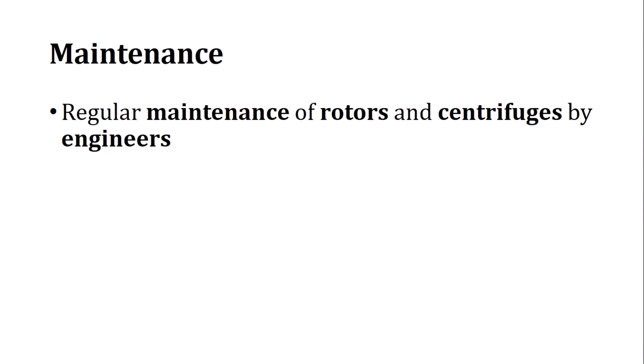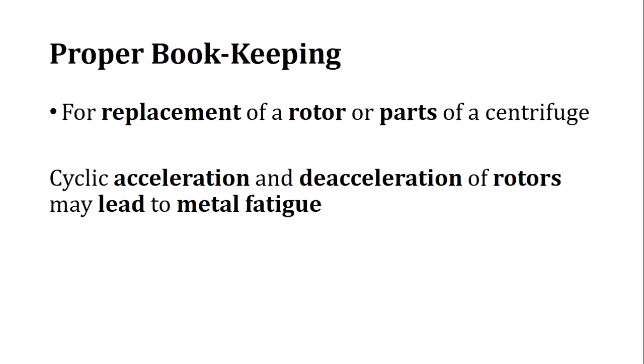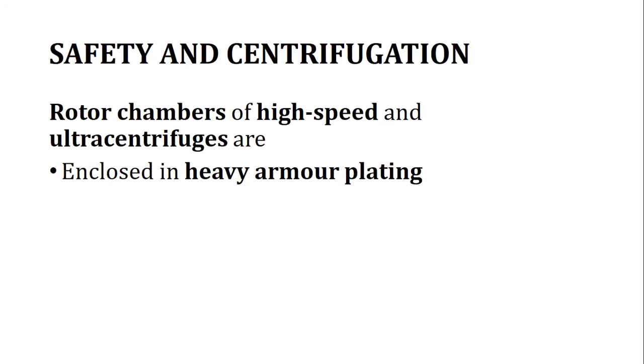Regular maintenance of rotors and centrifuges should be carried out by qualified engineers. During the warranty period, engineers may provide free services. Proper record-keeping for replacement of rotors or centrifuge parts should be maintained. There is also a phenomenon called metal fatigue caused by cyclic acceleration, so rotors should be changed periodically to avoid this.